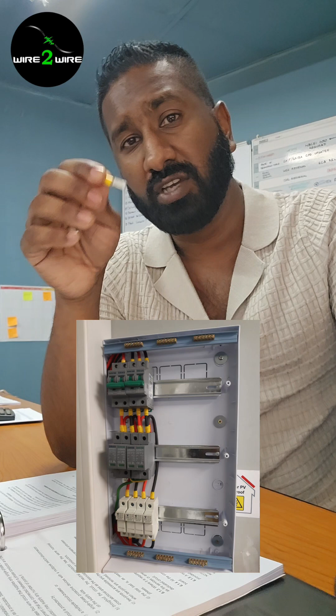Another thing we do is pre-wire all our distribution boards, AC and PV DBs, and all our PV DBs are wired using hook blade lugs. All cables in the PV DB are wired with this. It gives you an airtight crimp onto the cable, and when it goes into the breaker, it's a neat finish, and it helps mitigate the risk of hotspots and future failure of breakers.